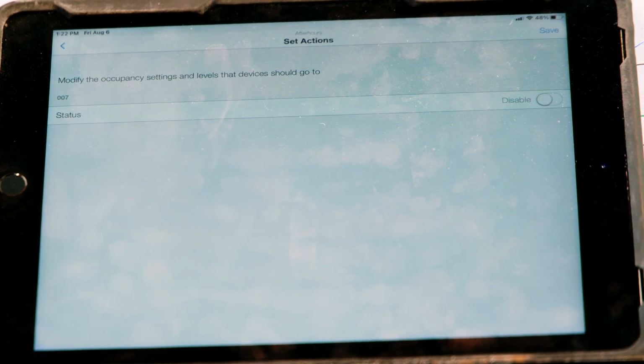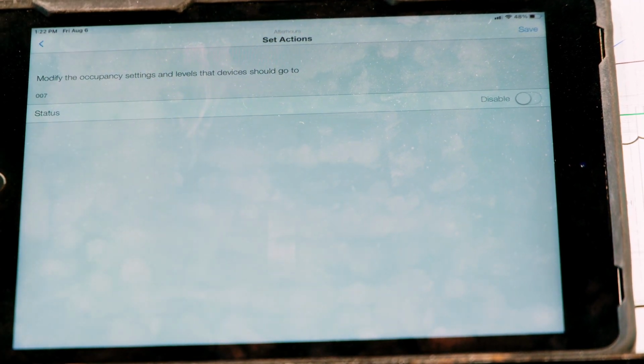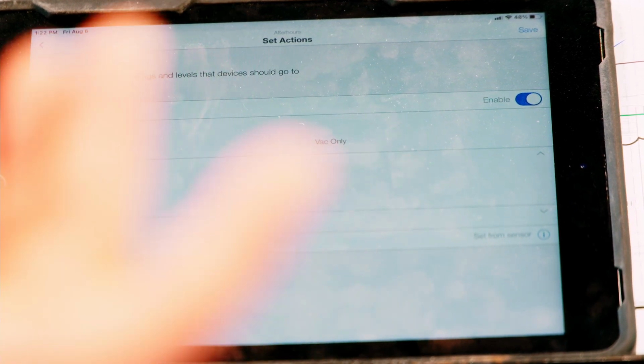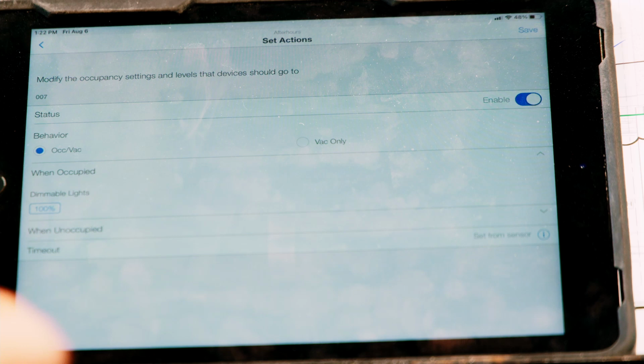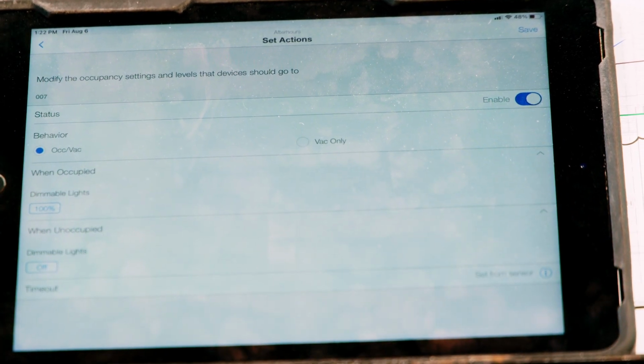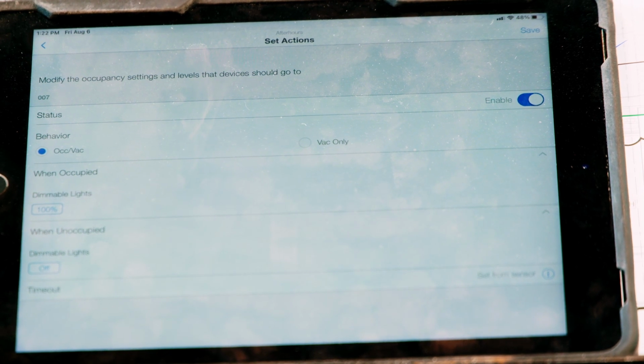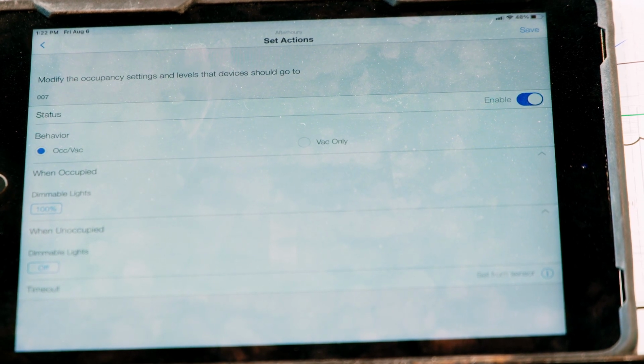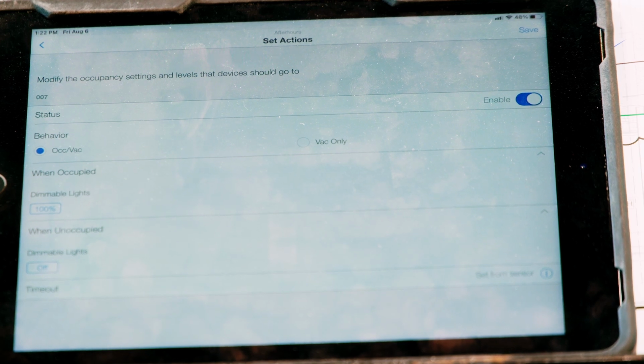So let's say in some applications that we do, you want to not have the occupancy sensor active during the day because you don't ever want to have the lights shut off, right? So when we're doing office environments, often from 9 to 5, they wanted to have the lights on. Or another thing that you can do, you can change what happens during that time when it's occupied or unoccupied. Another thing that you can say, during normal business hours, you want to have the lights dim to 20%, but after hours you want to turn the lights off when it goes unoccupied. So that flexibility is built into the system.